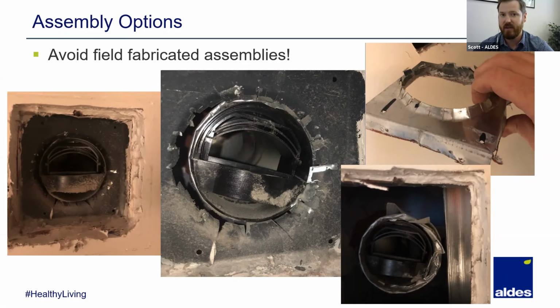Now, if you start to see errors within that, like I'm getting no flow at the bottom, but it's working fine at the top, then we can start to look at, okay, maybe there's a leakage issue. Maybe there's a big hole in the duct that somebody missed. Maybe we need to turn up the fan pressure. So if anything, during the troubleshooting process, a lot of people like to point at the airflow regulator as a source of the problem, but more often than not, they're a source of the solution. If everything's working and it allows the airflow regulators to work, then you know that the entire system is performing the way it's supposed to.